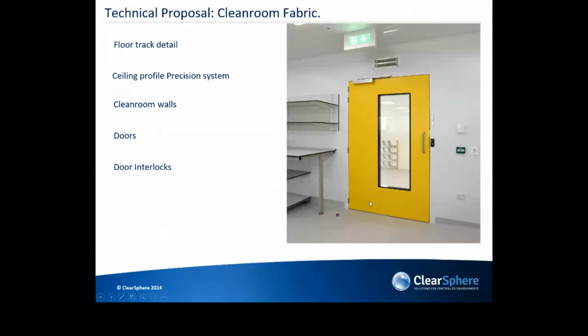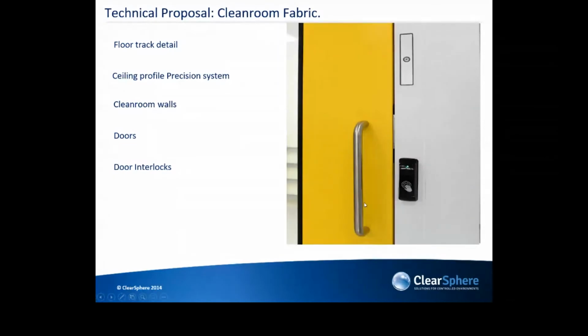From an interlocking perspective, coming from outside to inside through a lobby, the doors are interlocked with each other to ensure there's no clean path through to a classified area from a non-classified area. As part of that door interlocking design, we used contactless wave sensors to minimize contact surfaces, to help prevent any cross-contamination.